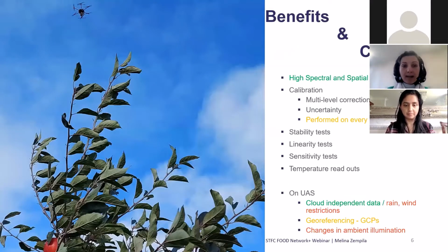Once you get your hyperspectral system, you gain on spectral and spatial resolution. As any other sensor, though, it requires its radiometric and geometric calibration as well in order to acquire accurate, or as accurate as they can be, and time-independent results. But one could be a bit flexible here and choose what type of radiometric calibration he would like to have. For example, if you convert to absolute radiance, then you won't have to perform the calibration imaging processing on every batch of data, which is something that at least we are doing when translating the raw data into reflectances.